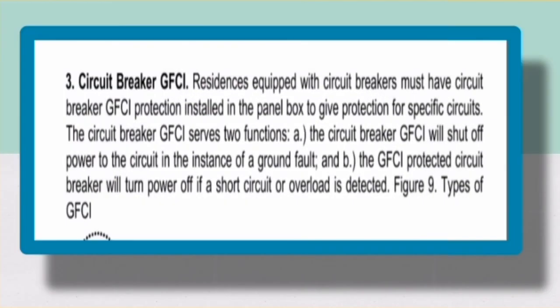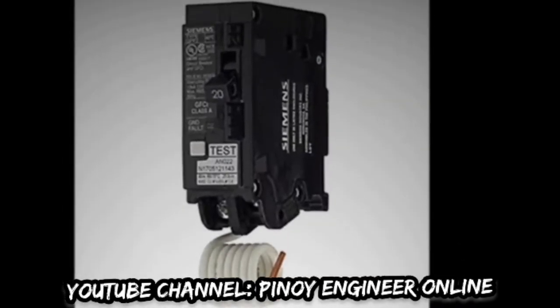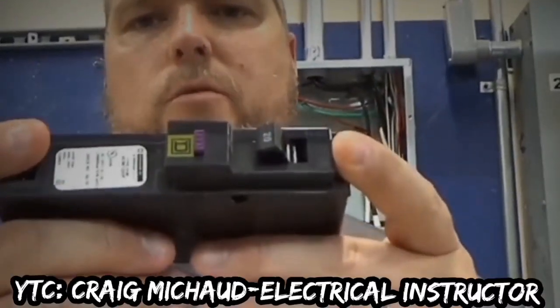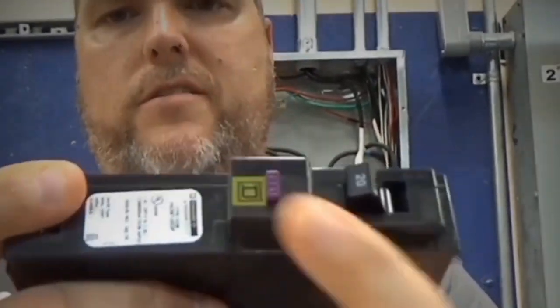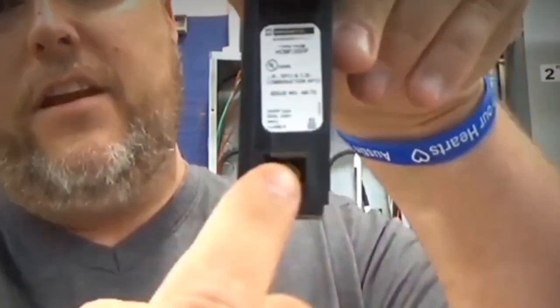Number three: Circuit Breaker GFCI. Residences equipped with a circuit breaker must have Circuit Breaker GFCI protection installed in the panel box to give protection for a specific circuit. The Circuit Breaker GFCI serves two functions: first, it will shut off power to the circuit in the instance of a ground fault; and second, the GFCI circuit breaker will turn power off if a short circuit or overload is detected. On a GFCI breaker — this happens to be a Square D — this is a 20-amp breaker. You have your trip button here, which is purple on this one and says 'trip' so you can't miss it. On this long end is where the mechanism is for the ground fault protection.